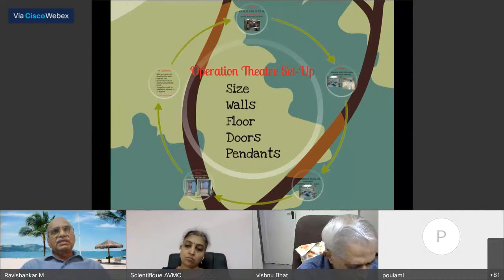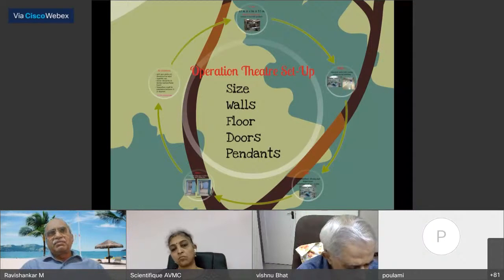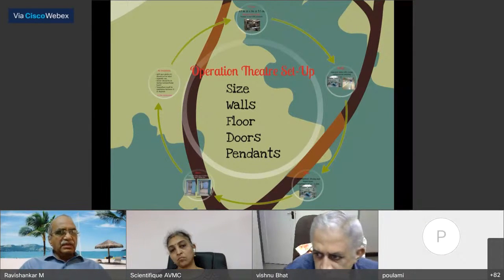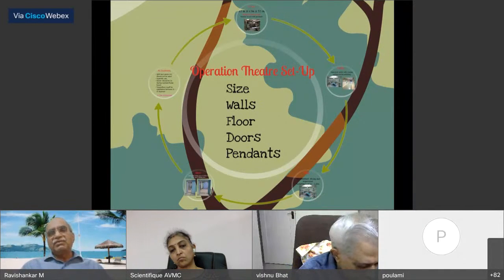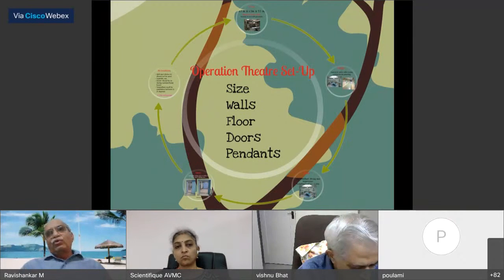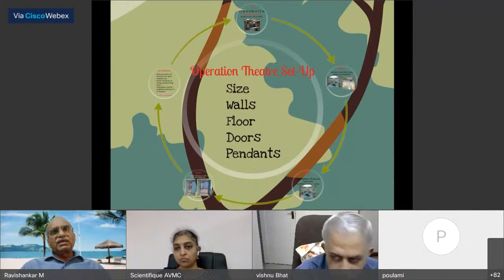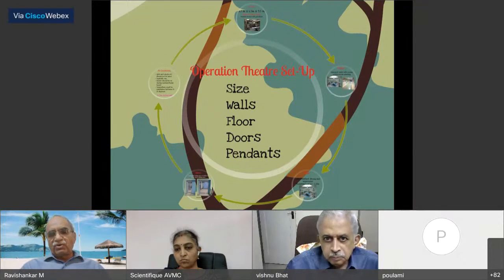So this same laminar flow system is incorporated along with another exhaust system, so that the pressure inside the theater is maintained negative, and then the blower capacity has to be increased to match the exhaust system. So a lot of readjustments have to be done, which in most places has not been carried out, but that is what has been recommended, especially for COVID OTs which are designated like that.